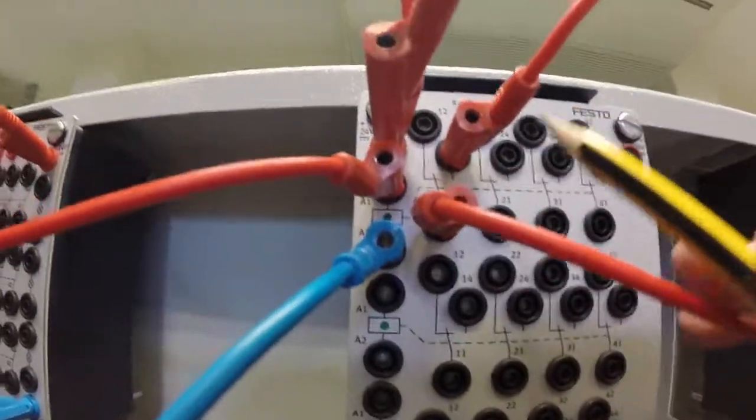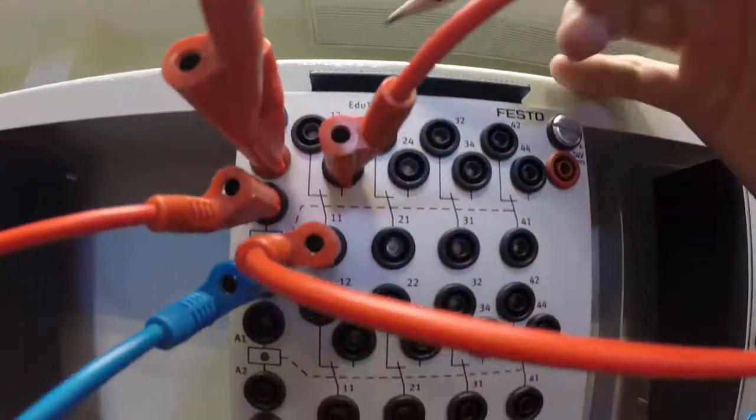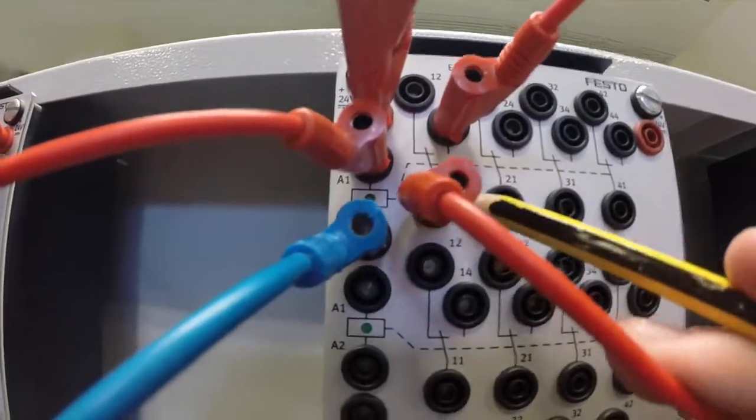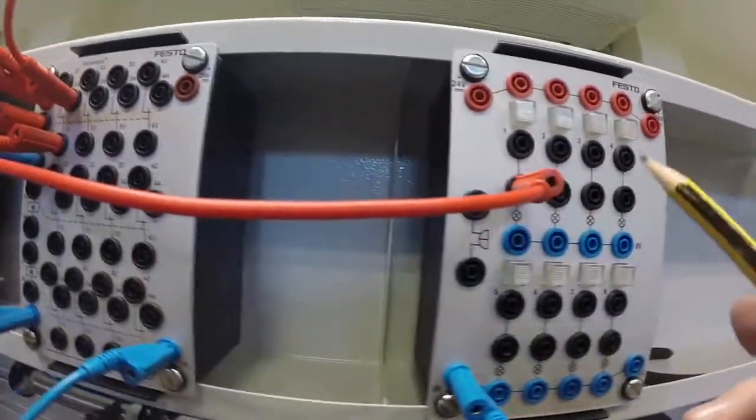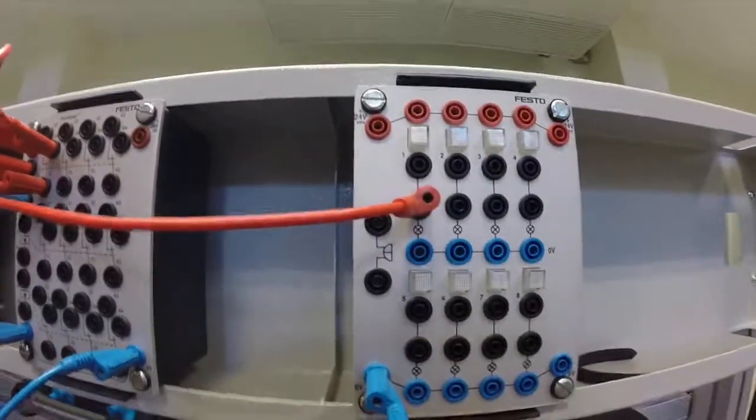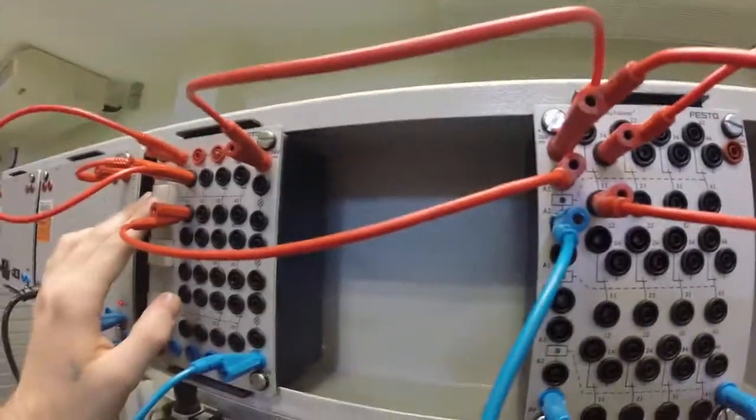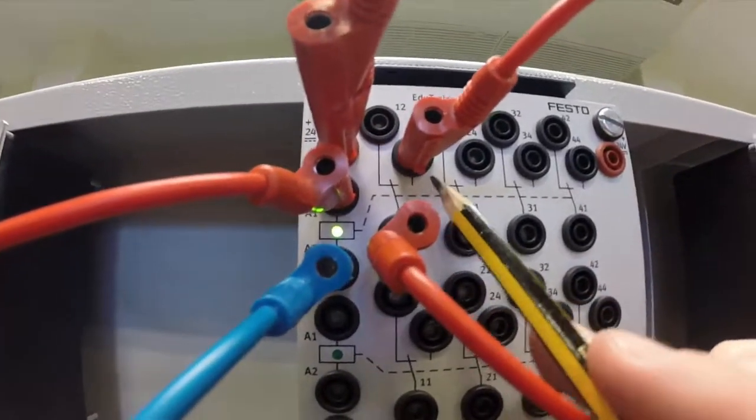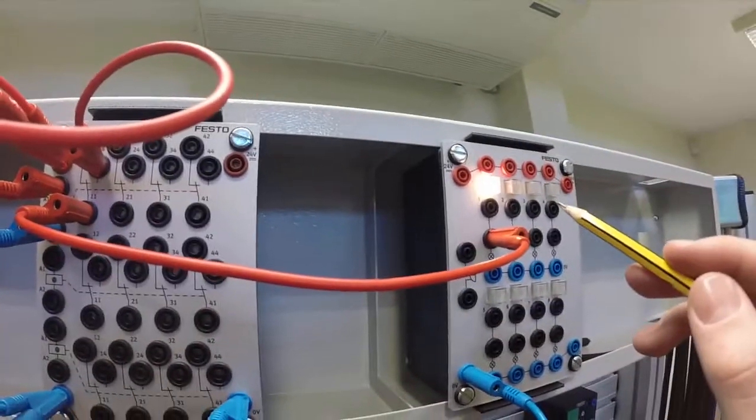What we're doing with the contacts of the relay is we have got contact number 14. So a normally open contact is being connected into 24 volts. And then the other end of the normally opened, the 11, is going into our output over here, which is our light. And then that is getting grounded out. So we have another closed loop there. So you'll see once we operate the switch, the relay contacts will have crossed over. So now the connection will be between 11 and 14 and the light will come on.